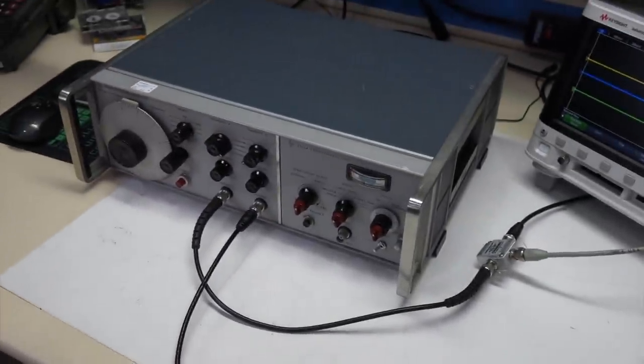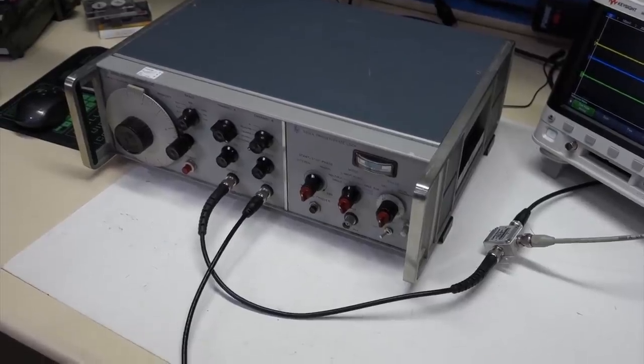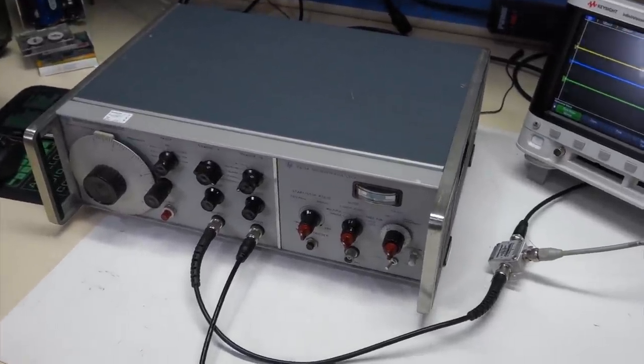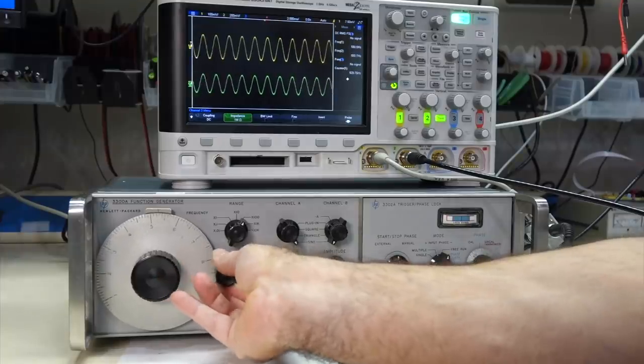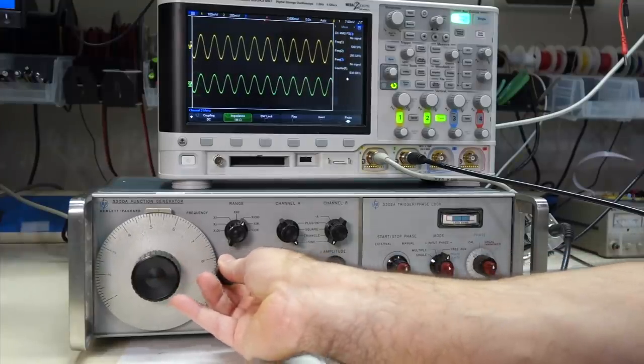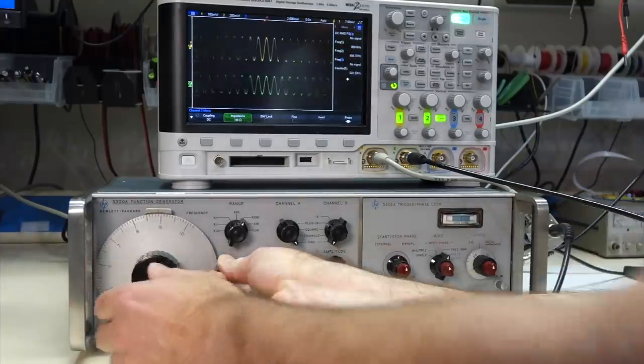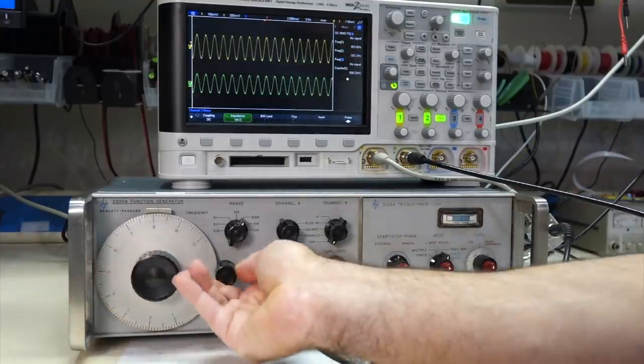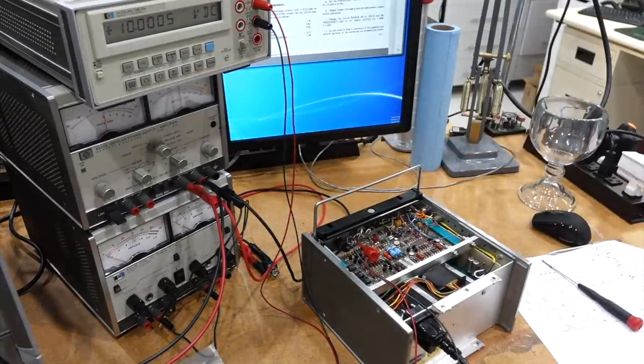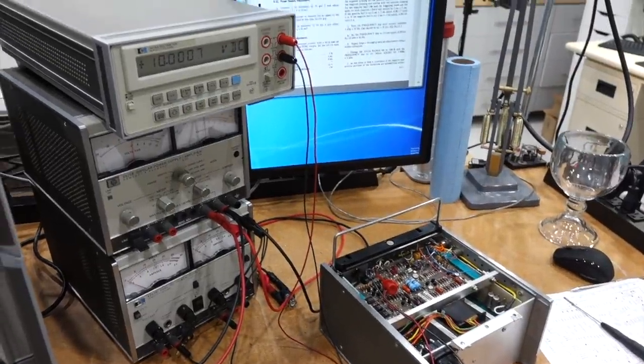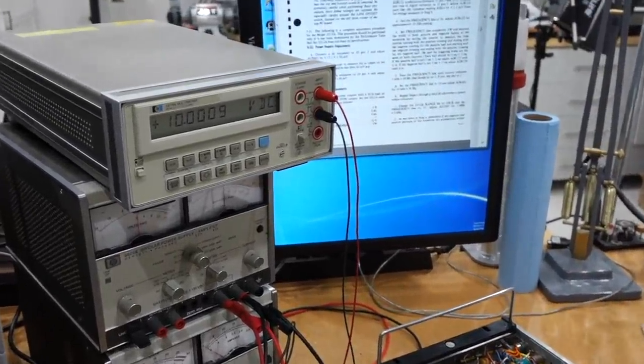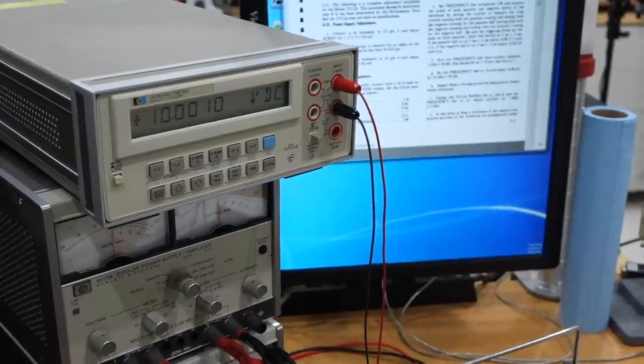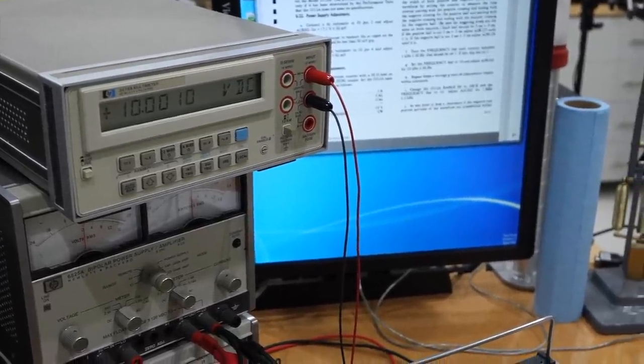These are old analog instruments which have often been neglected. They have many fine adjustments and usually need to be fully recalibrated before they perform as intended, which for HP is usually pretty tight, within a percent or two of ideal. And that's how it started with the HP 3300A.